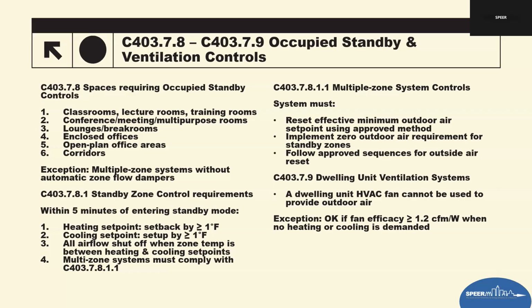The code requires 3 actions. Heating setback of at least 1 degree, cooling setup of at least 1 degree. This widens the deadband to reduce cycling. And then shut off air supply whenever the temperature is between the heating and cooling set points.